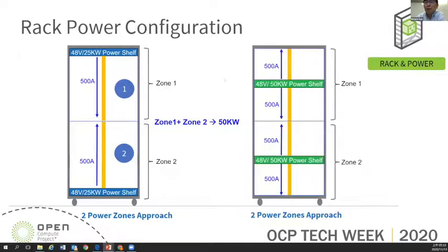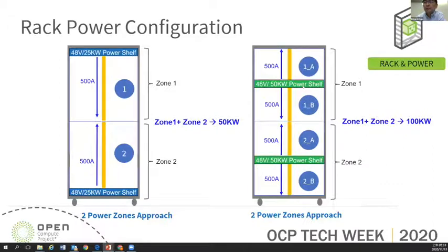But however, if we put the power shelf in the central location between zone 1 and zone 2, I think zone 1 can handle the current. Right now it becomes 500 amp plus 500 amp, around 1,000 amp. So each power zone can handle 50 kilowatt. So zone 1 and zone 2 can handle around 100 kilowatt. So I think that means we can have the complex size 48 volt power, 50 kilowatt power shelf, and put 2 power shelves in the V3 open rack. Then we can build a 100 kilowatt open rack.